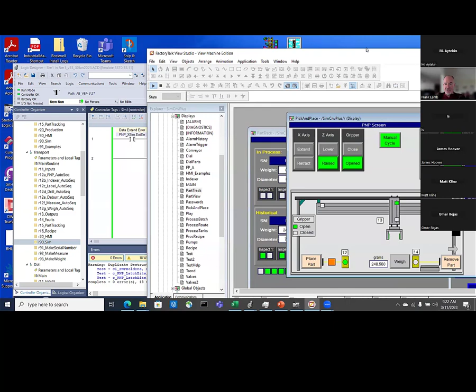You see the sensors riding on here. So that simulation AOI is what makes the sensors change state. You can see here it's at the end, so the prox is on. And everybody has a different way of emulating these. One of my things is I do not like red objects on my main screen. In process control, sometimes people do that. They put red for something operating. But in machine control, usually red means something bad. It's an alarm or a fault or something like that. So I don't make my sensors turn red when they get made. But some people will, right? Some industries, that's a common thing to do.